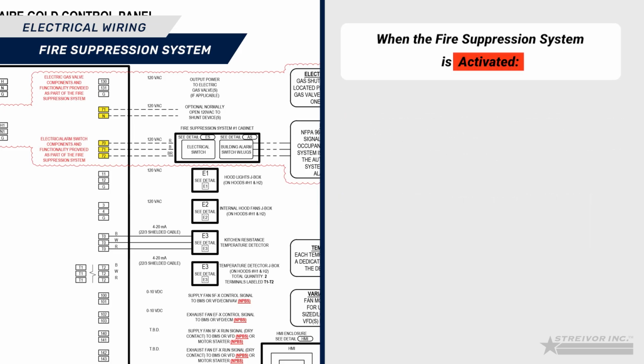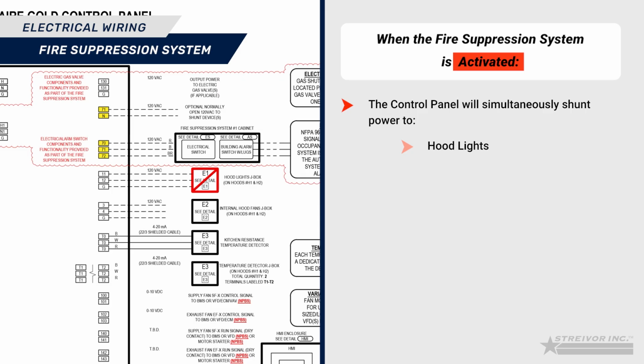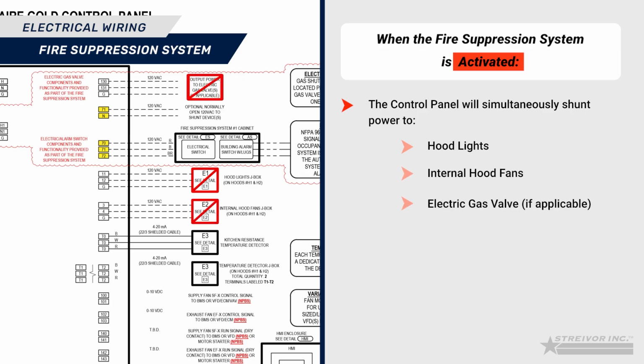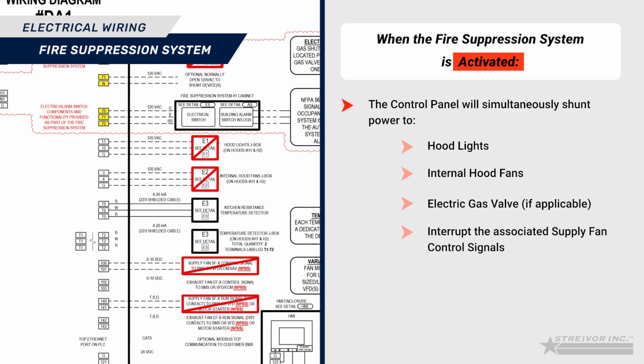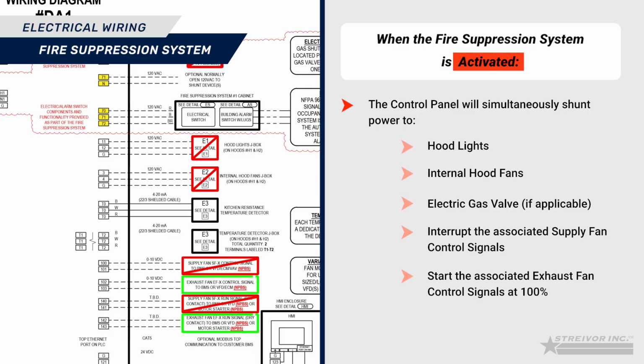When the fire suppression system is activated, the control panel will simultaneously shunt power to the hood lights, internal hood fans, electric gas valve if applicable, interrupt the associated supply fan control signals, start the associated exhaust fan control signals at 100%, and apply 120 VAC power to the normally open shunt terminals.